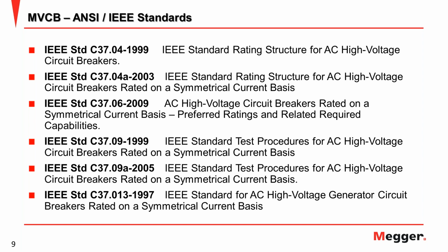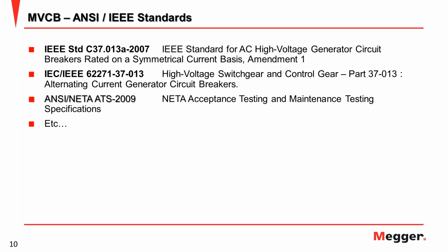And the other famous standard is IEC or IEEE 62271-1. This is for high voltage switchgear and controlgear. Here you can also see the testing procedure, criteria, and definitions of any description of the breaker. And the ANSI or NETA standard can also be used for your reference regarding circuit breaker tests, to define things like the minimum voltage to be used for testing, like a hipot, or the contact resistance value. So you can see this in the ANSI-NETA standard, and still many more standards can be used for your reference.